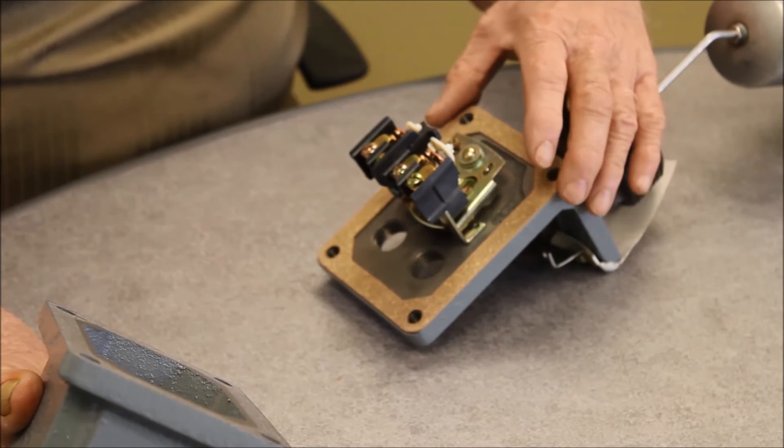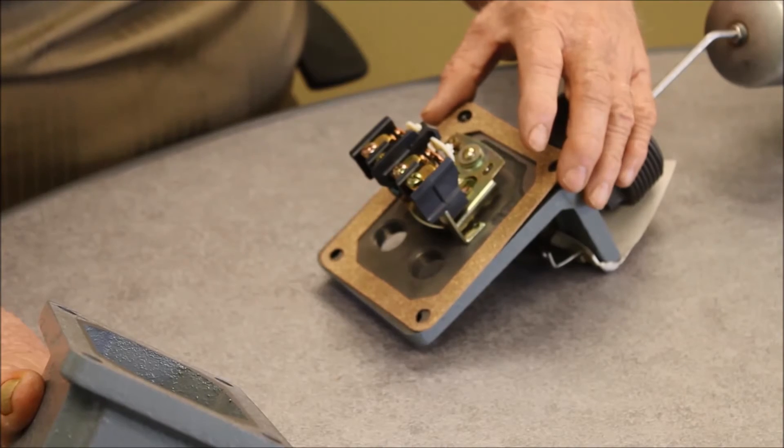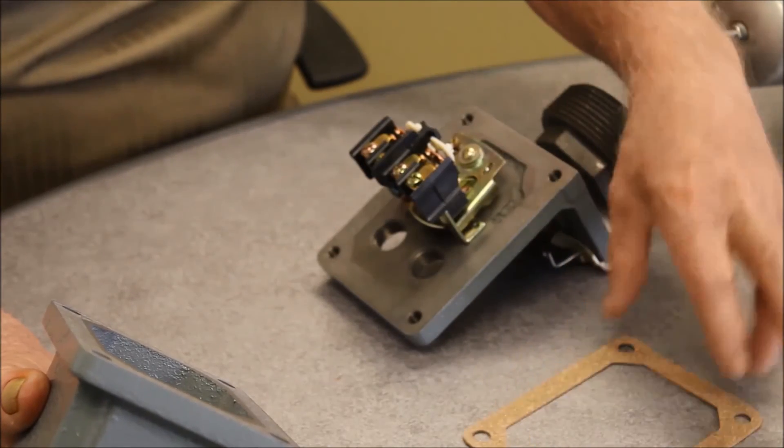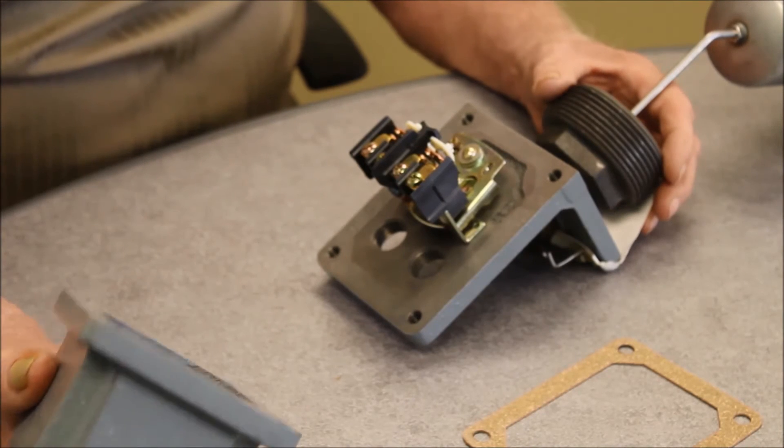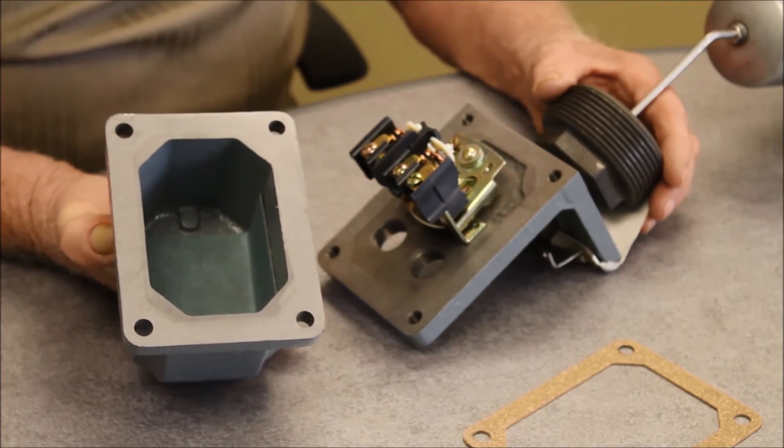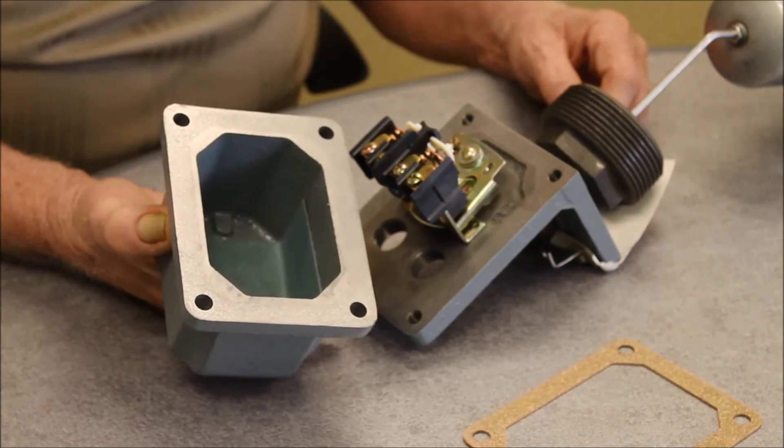Installing a gasket on a NEMA 7 and 9 will destroy the hazardous location rating and should never be done. A NEMA 7 and 9 device is machined for a tight fit to allow controlled escape of gases and should never ever be gasketed.